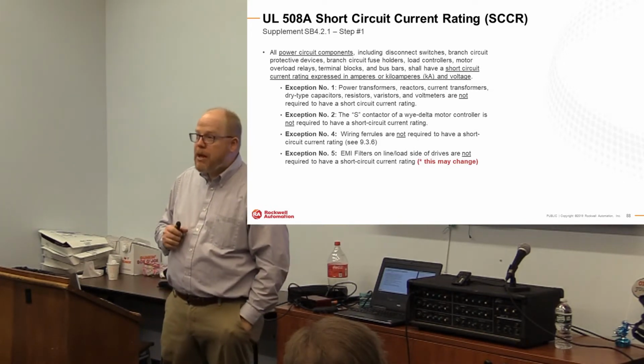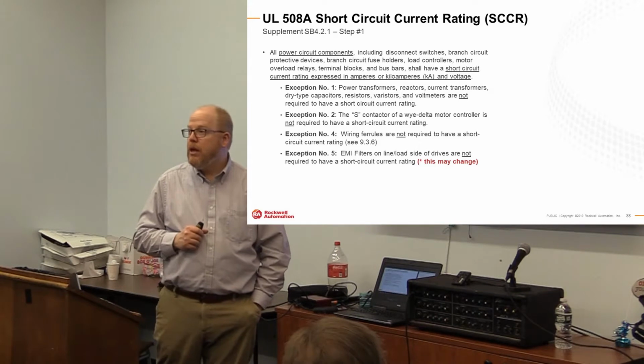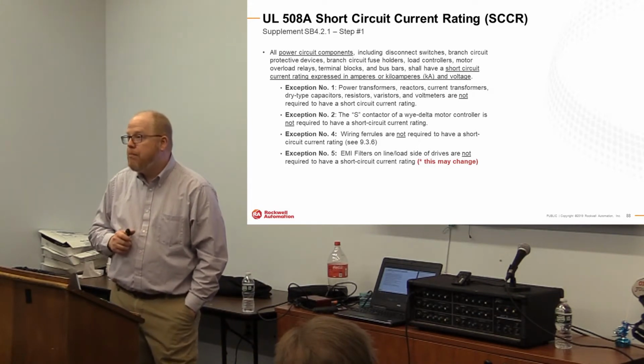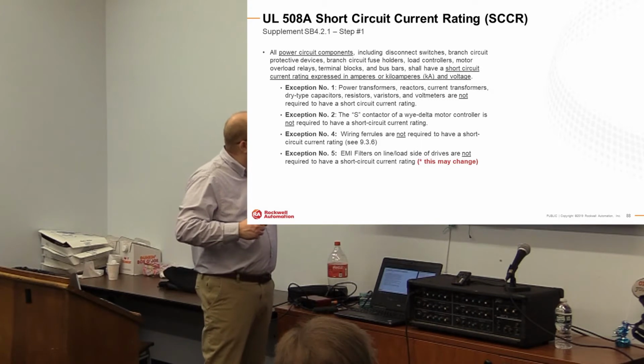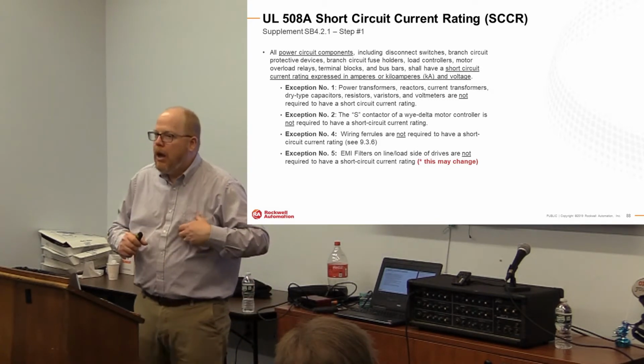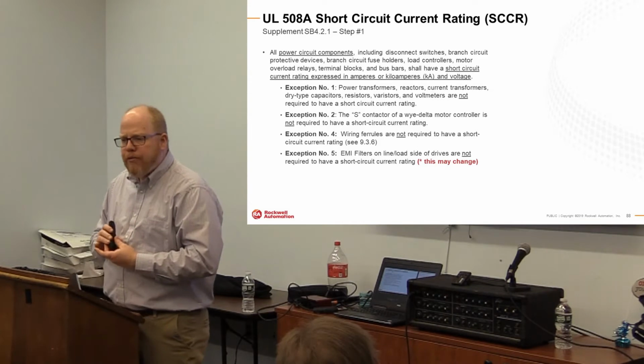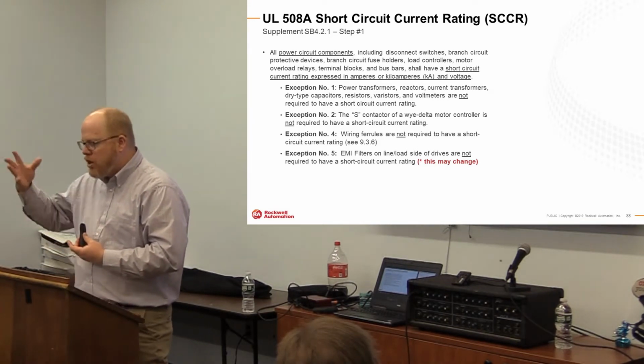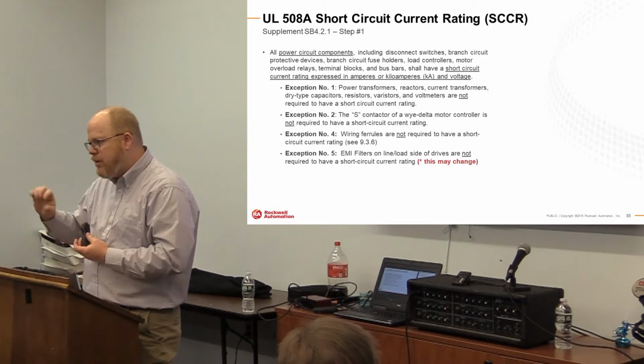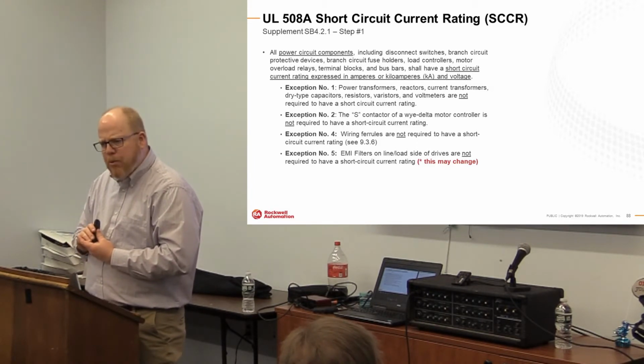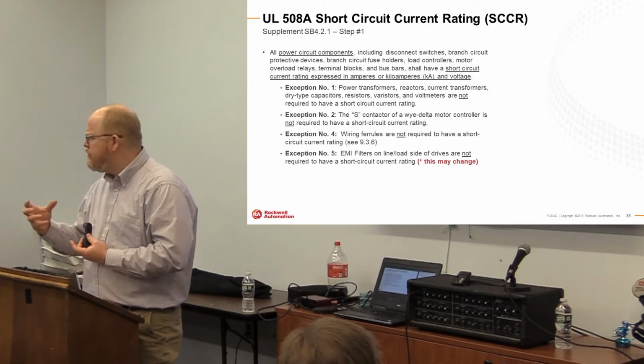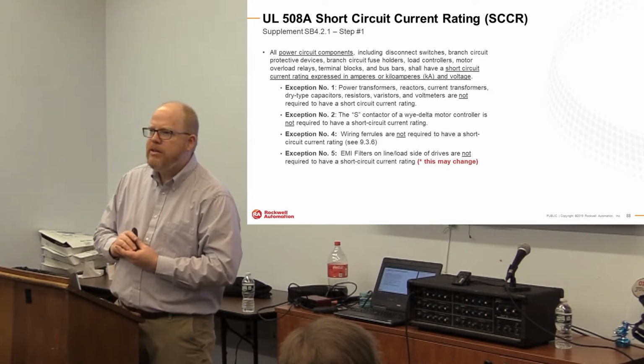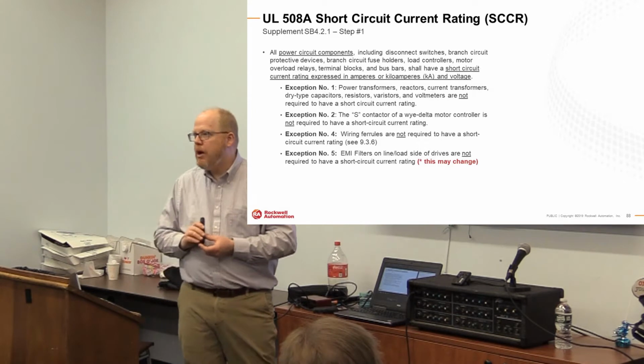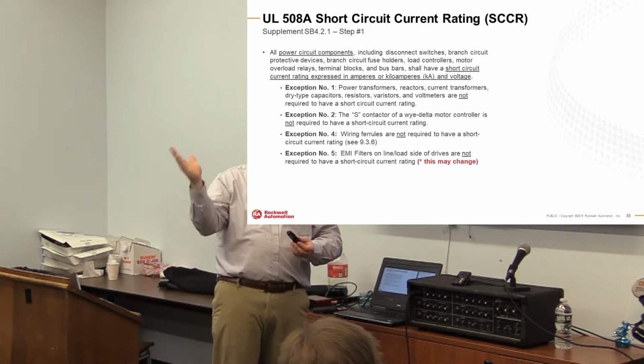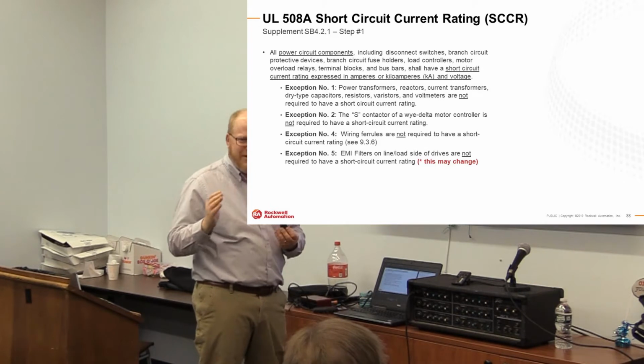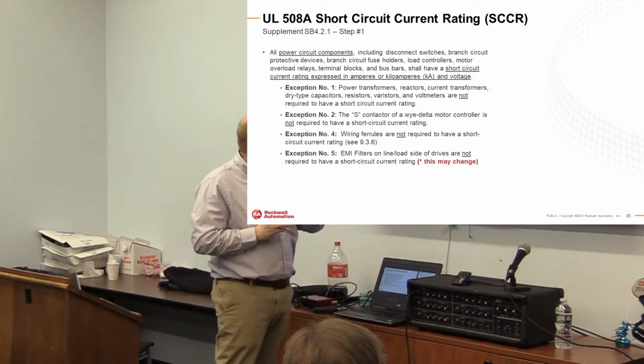Now there's a handful of exceptions here, like power transformers and reactors and things like that. Very important is number 4. For those of you who use ferrules, and some do, some don't, for many years, people were asking, ferrules, which are crimp-on lugs for stranded wire, does that impact my short circuit current rating if I use ferrules on my feeder wire? It does not. Okay, that's clear now. It had several volleys of different answers to that. They have clearly gone in the exception here and said it does not.